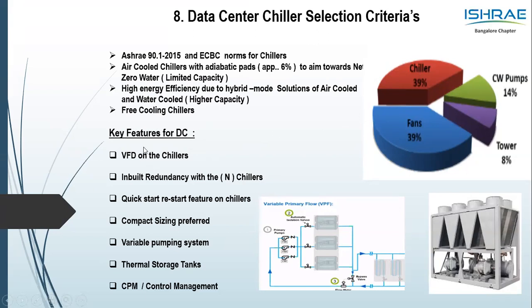A couple of very important key features when you select a chiller: VFD on the chiller because it's catering to a DC space. Inbuilt redundancy, we spoke on tier, and also the redundancy saving. So redundancy is applicable very much for a chiller. Quick start, restart, very important. We don't want downtime there. We want the DCs to be up and running. Options like the variable pumping system go into the chiller as you select it, and a couple of other options like a chiller plant optimizer or manager, and having a thermal storage tank could actually save on your OPEX.